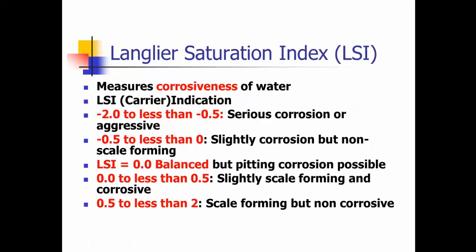The Langelier index measures the corrosiveness of the water. So the thing that you need to know is if it's got a minus in front of it, it's aggressive, it's acidic. And if it's above that, then you get scaling. And here's the levels where you get different levels of scaling and your corrosion in your lines.